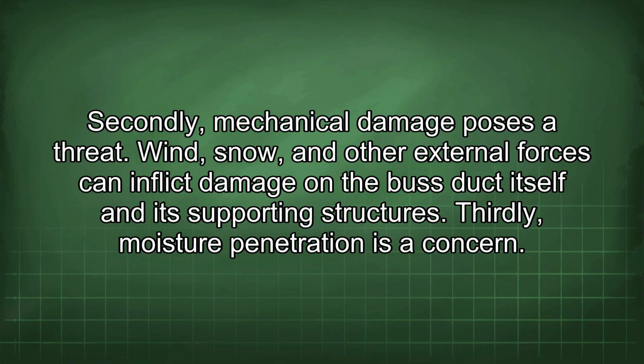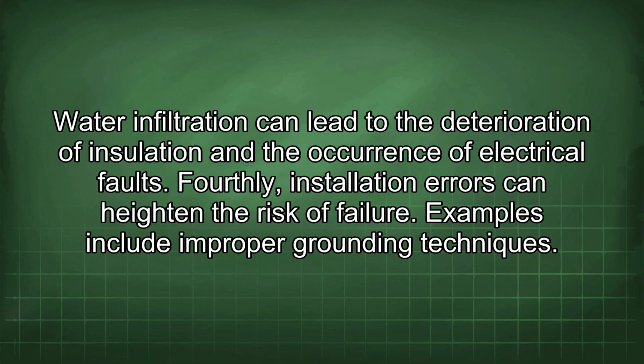Secondly, mechanical damage poses a threat. Wind, snow, and other external forces can inflict damage on the bus duct itself and its supporting structures. Thirdly, moisture penetration is a concern. Water infiltration can lead to the deterioration of insulation and the occurrence of electrical faults. Fourthly, installation errors can heighten the risk of failure. Examples include improper grounding techniques.